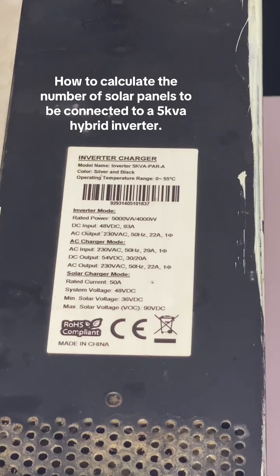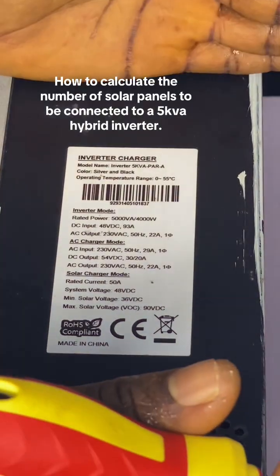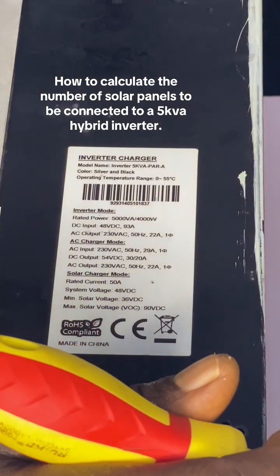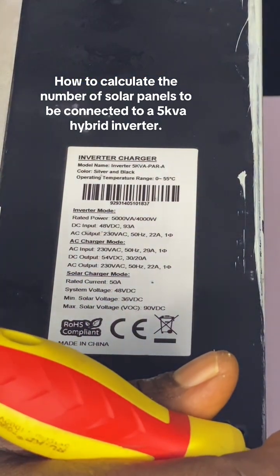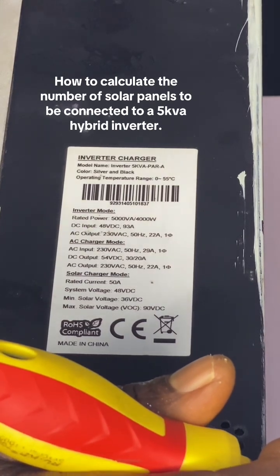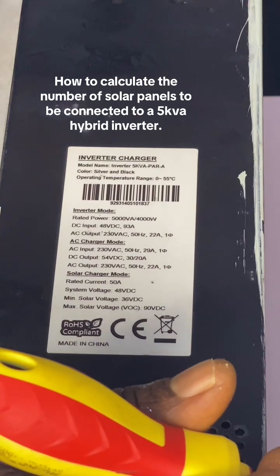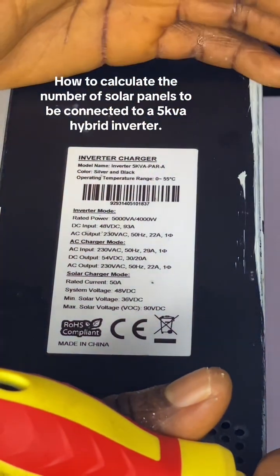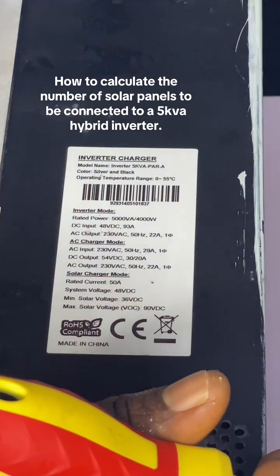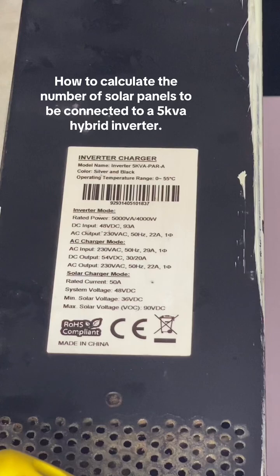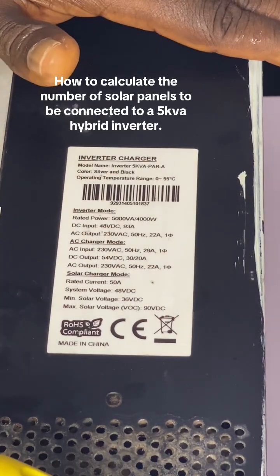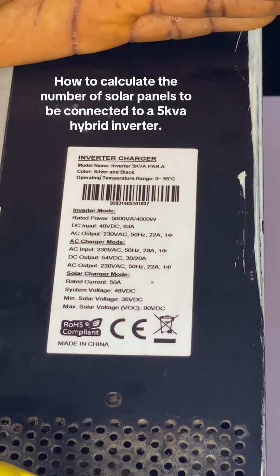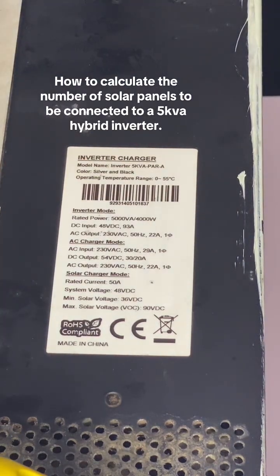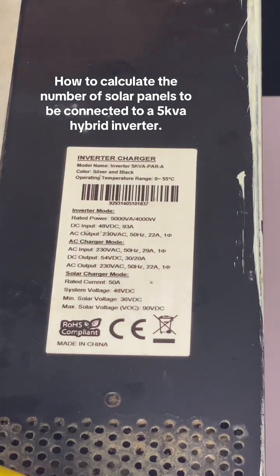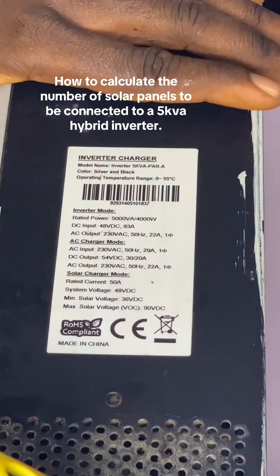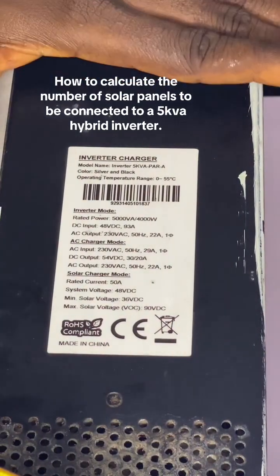So to know how many panels we can connect to this inverter, we will have 4 strings: 2 panels in series, another 2, another 2, and another 2, making 4 strings. That means the total number of panels this inverter can handle is 8 panels. We must not go beyond 8 panels, or there is a high probability of damaging the inbuilt charge controller.